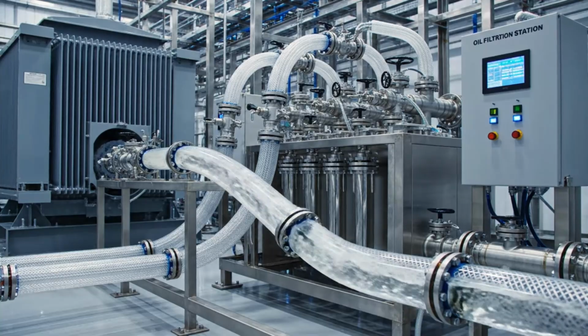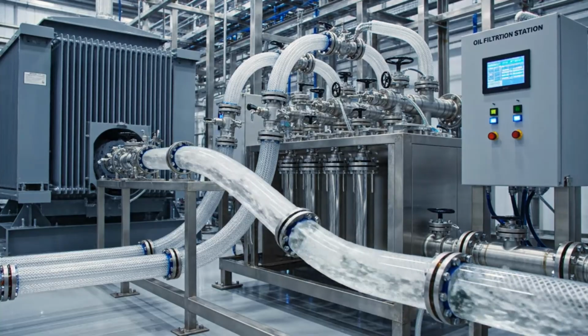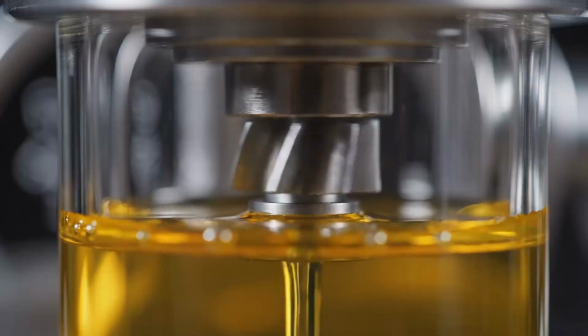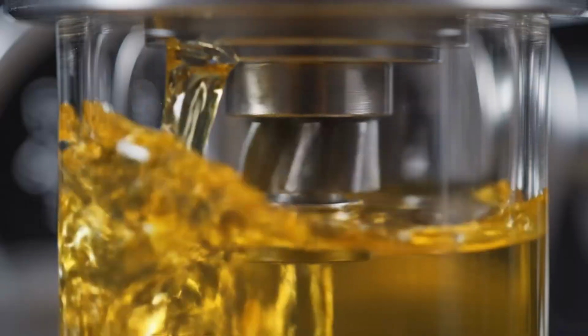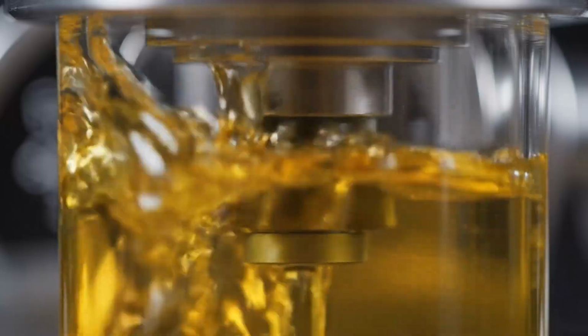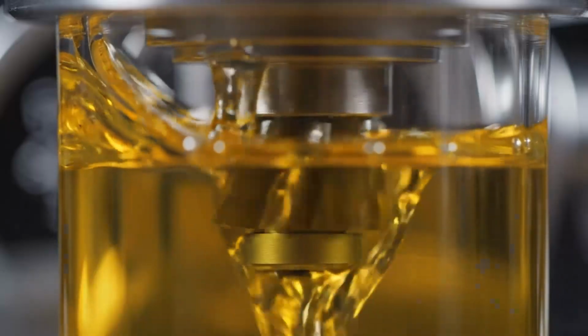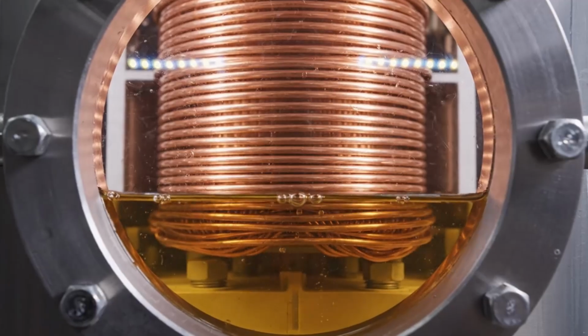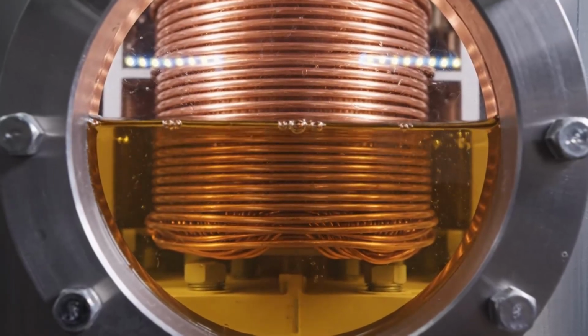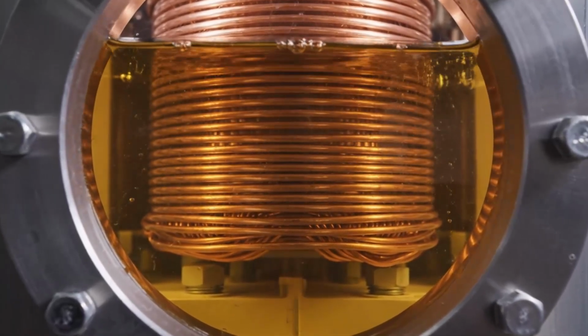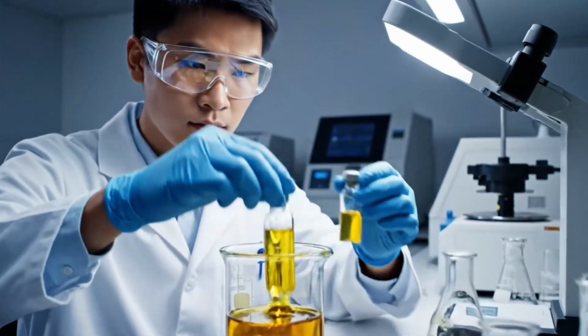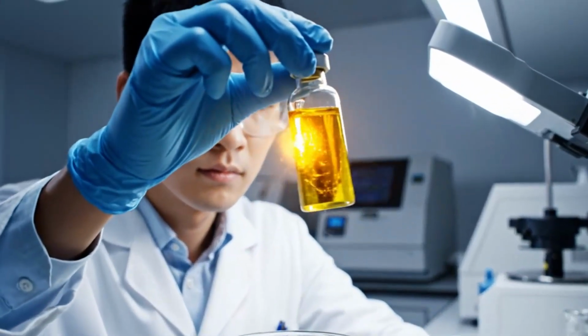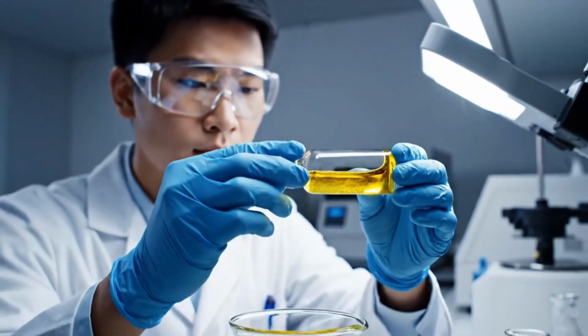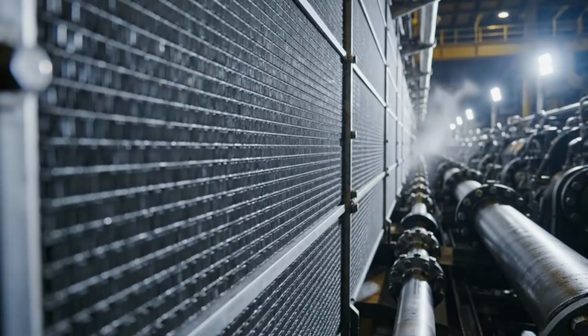The active part is placed inside a massive vacuum chamber, or a vapor phase autoclave. Here, the pressure is dropped to near vacuum levels while the temperature rises. The goal is to extract every single atom of water from deep within the fibers of the paper and wood insulation. This process can last for days, and the wait is agonizing but essential. This is the baptism of the transformer, preparing it to withstand decades of heavy-duty service.